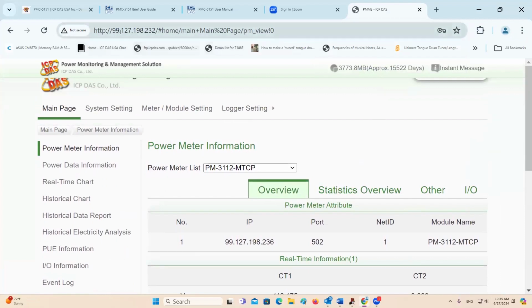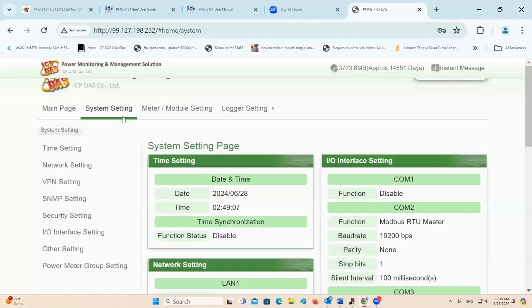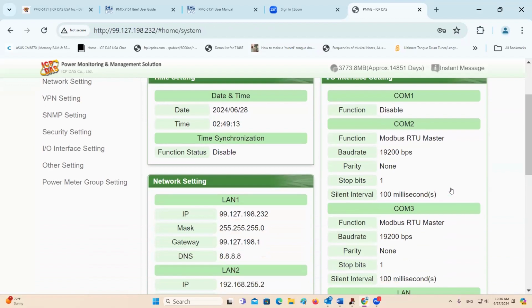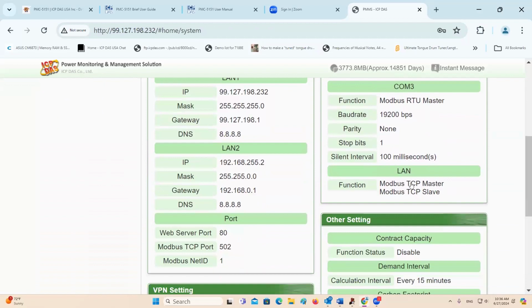You basically type in the URL, the IP address that you set up, give it a password, and then you have the opportunity to set up under system settings. If you're going into any power meters that were over Modbus RTU, you've got your COM2 and COM3 to set up. You also have the option of Modbus TCP, and the power meter I was just showing you data from is the one over Modbus TCP.